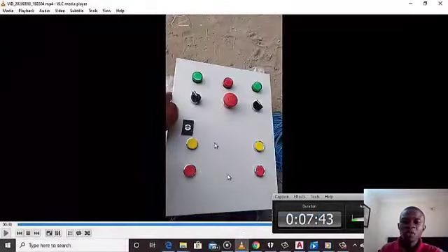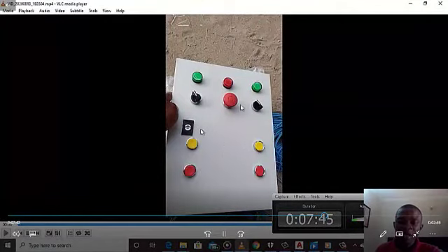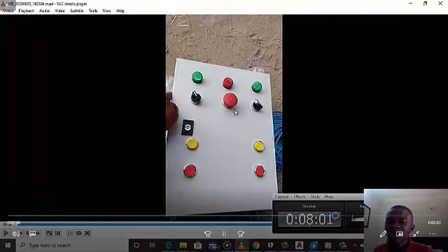I'm going to show you the front. This is the front of my panel. When I say override, once you press this emergency stop, it overrides the automatic side of the operation, which means you have to turn this switch to generator and press your start button. Generator will be energized, or you turn this and press, and public power will be energized, showing you the one that is available. And this is load run, that is, load you have engaged.